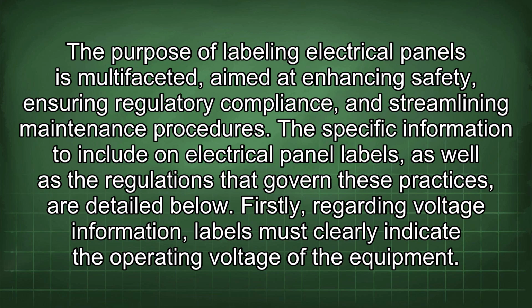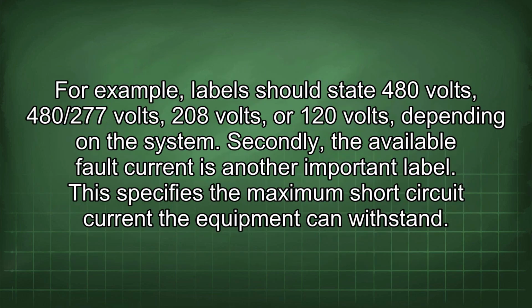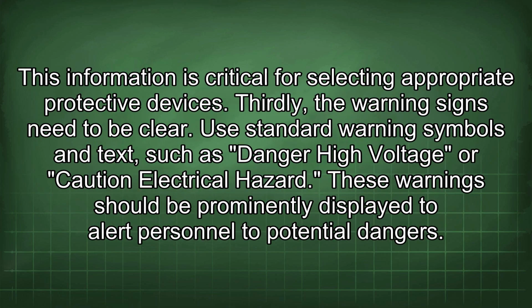The specific information to include on electrical panel labels, as well as the regulations that govern these practices, are detailed below. Firstly, regarding voltage information, labels must clearly indicate the operating voltage of the equipment. For example, labels should state 480 volts, 480/277 volts, 208 volts, or 120 volts, depending on the system. Secondly, the available fault current is another important label. This specifies the maximum short-circuit current the equipment can withstand. This information is critical for selecting appropriate protective devices.